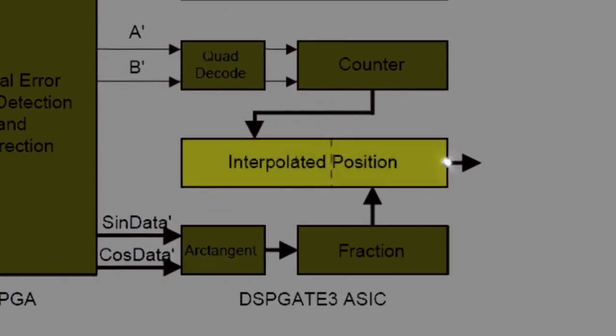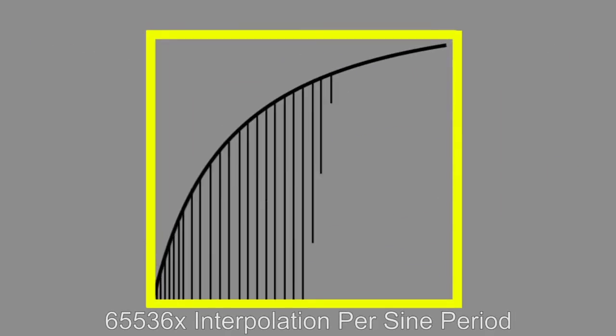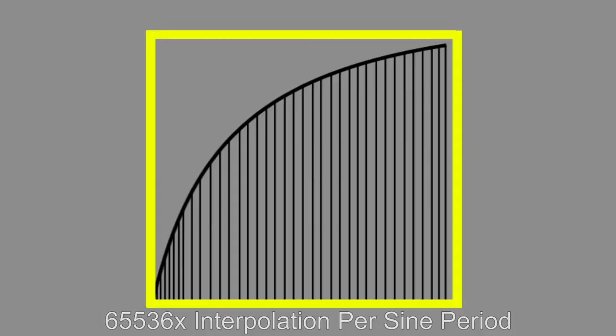The interpolator will accept these signals directly and then divide each line of the encoder into 65,536 individual distinct states. This provides for an unprecedented level of resolution in a feedback device.